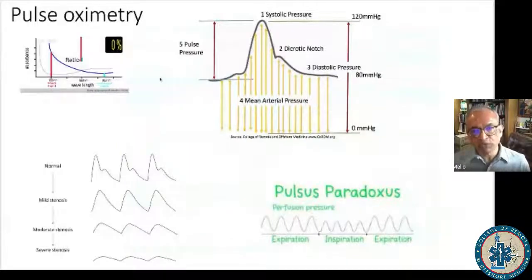Now, I just want to cover a few things about pulse oximetry. Remember, pulse oximetry uses 2 different wavelengths, red light and infrared light, and it assumes that the body contains only 2 types of hemoglobin, oxyhemoglobin and hemoglobin. Therefore, when you start getting more exotic hemoglobins like carboxyhemoglobin or methemoglobin or sulfhemoglobin or cyanhemoglobin, you're going to get abnormally high levels.